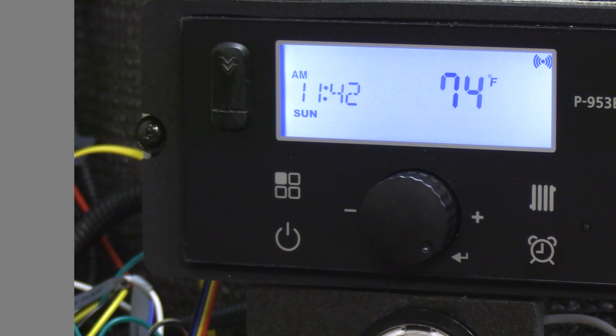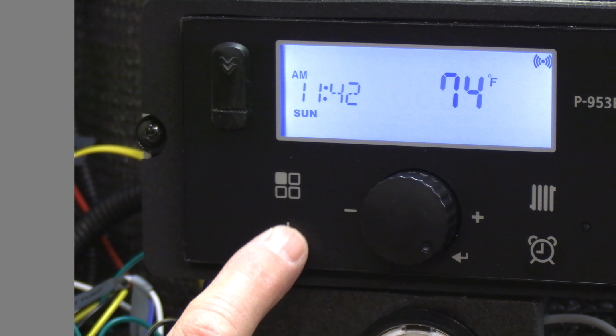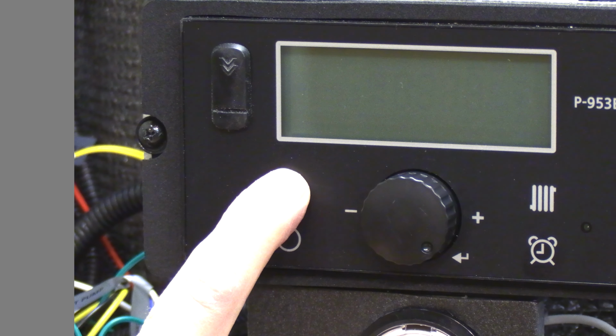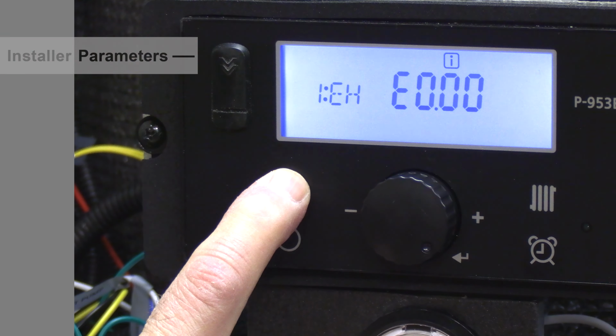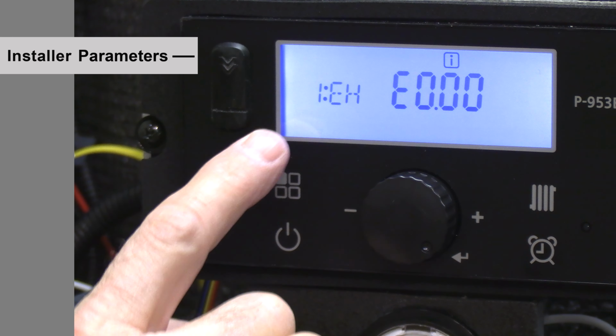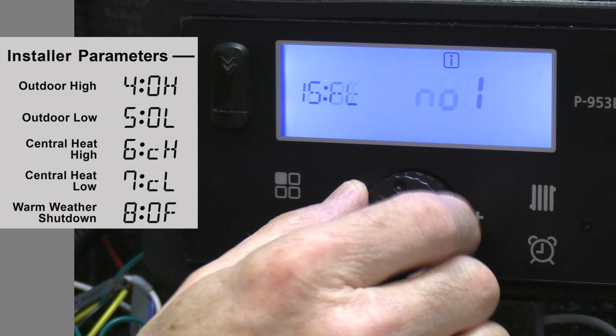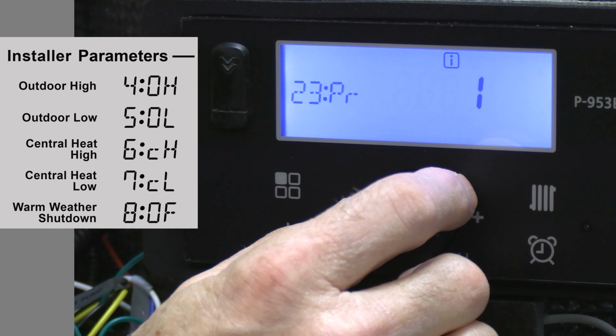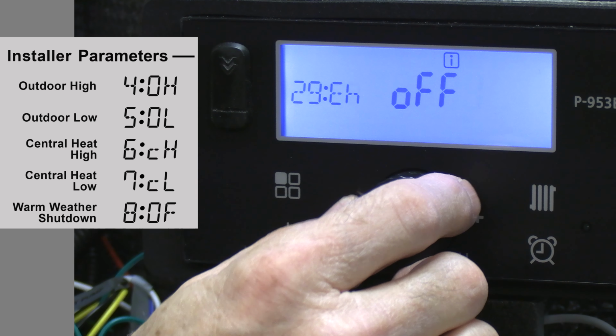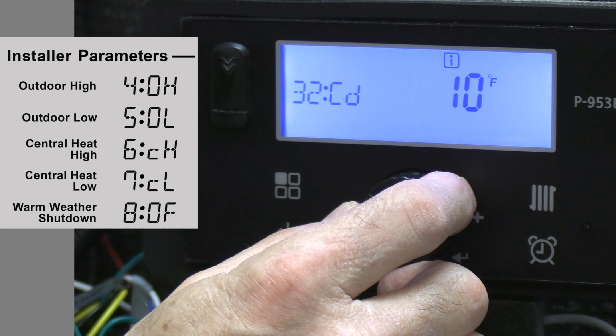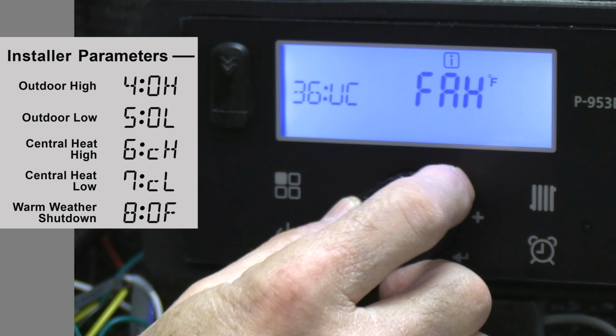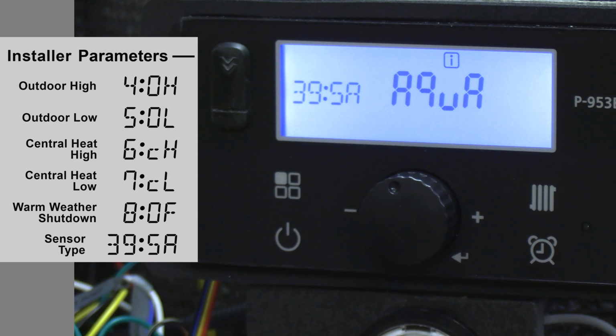Now, if you have an indirect tank, and again, we've set up our central heat with our outdoor reset, now what we want to do is get into the indirect tank. So again, I need to get back into that mode button, so what I'm going to do is power it off, press and hold the mode button until my display livens up. And on your indirect tank, we're going to go to parameter 39, okay? Parameter 39 is whether you have an aquastat or an NTC sensor. In parameter 39, it's defaulted for aquastat.